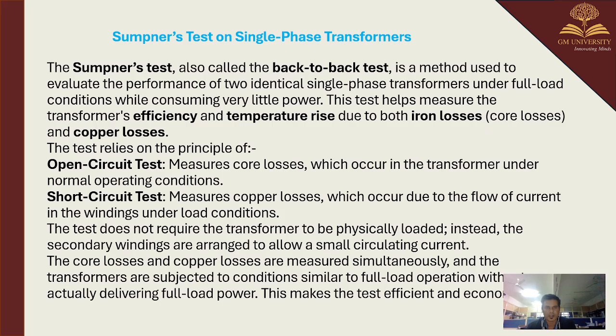So theory: the Sumpner test on a single phase transformer is also called a back-to-back test. This method is used to evaluate the performance of two identical single phase transformers under full load conditions while consuming very little power. This test helps us to measure the efficiency and also the temperature rise due to both the iron losses and the copper losses. The principle behind the open circuit test also comes into the picture, that is, we can measure the core losses which occur in a transformer under normal operating conditions. Under the short circuit test, we can measure the copper losses which occur due to the flow of current in the windings under loaded conditions.